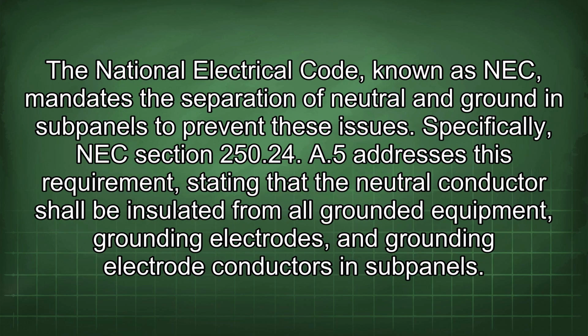The National Electrical Code, known as NEC, mandates the separation of neutral and ground in subpanels to prevent these issues. Specifically, NEC section 250.24(A)(5) addresses this requirement, stating that the neutral conductor shall be insulated from all grounded equipment, grounding electrodes, and grounding electrode conductors in subpanels.